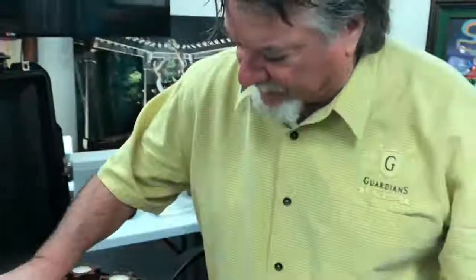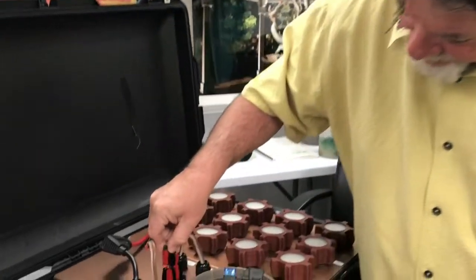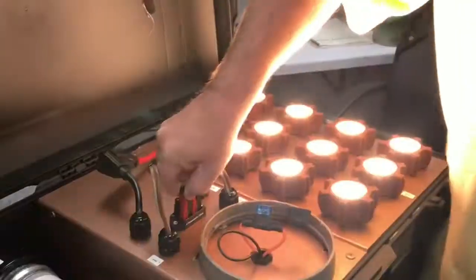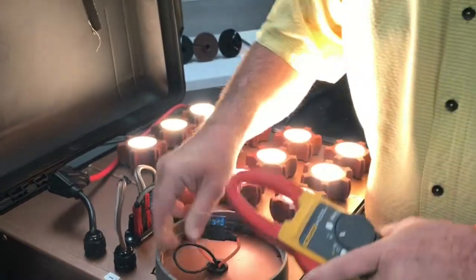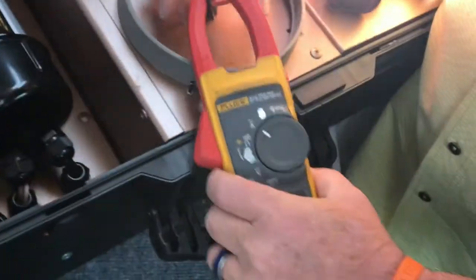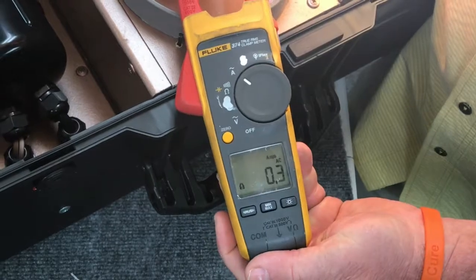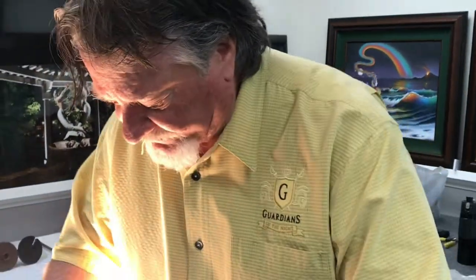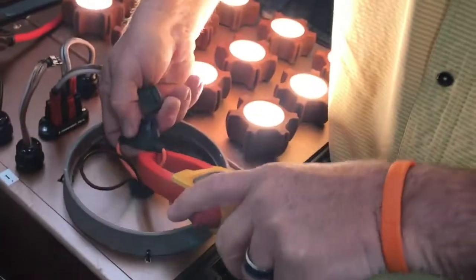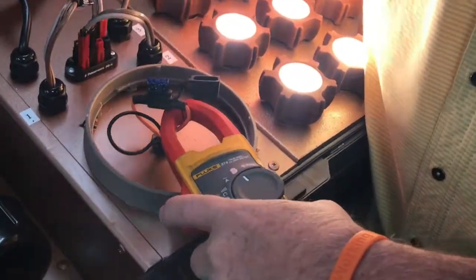I'm now going to compare that with my high efficiency transformer. I'm disconnecting and connecting, and coming over to my primary. You know it was 0.5, and now it's 0.3 - it's 80% more efficient, 75 to 80% depending how you calculate it. Then I'm going to come over here to my secondary. It was 4.2, and now it is 2.2 - right at 100% more efficient.